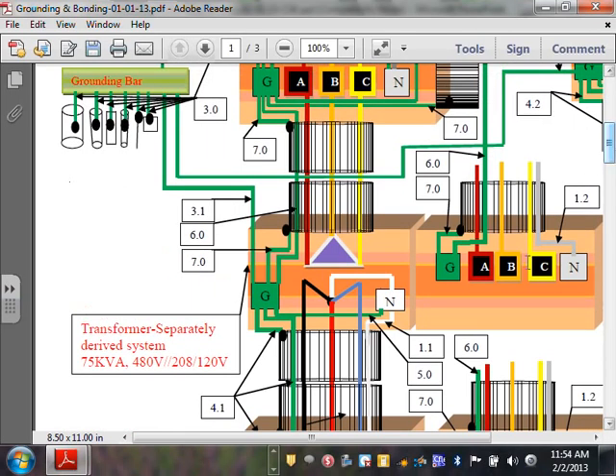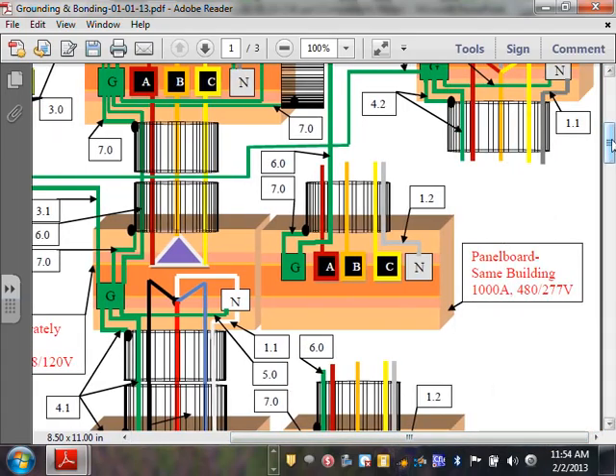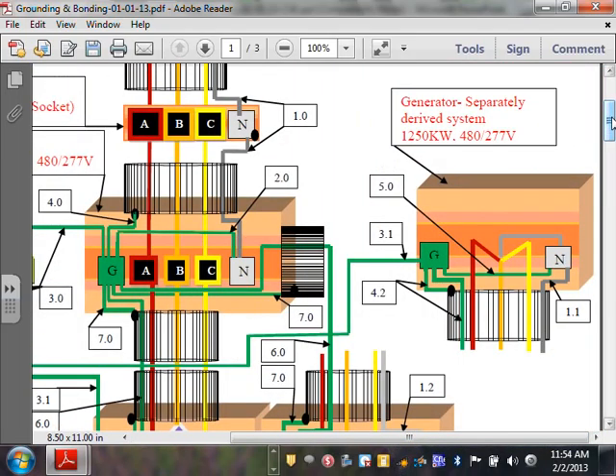Or multiple breakers on the generator. Now you put your breaker on the generator right here. That little piece, that wire here, becomes an equipment grounding conductor. If you put the breaker right at the generator, your overcurrent protection device right at the generator, now this piece becomes an equipment grounding conductor, and you size it based on the size of the generator overcurrent protection device. Okay. But in this scenario, because of the size, my circuit breaker is sitting right in here, inside the switchgear. This is supply side bonding jumper.